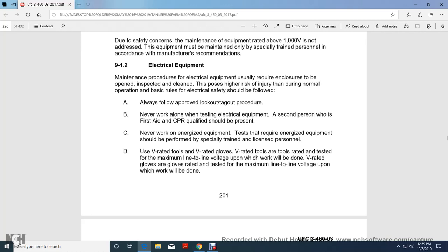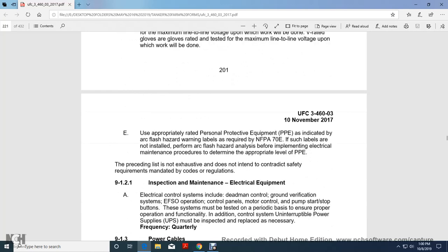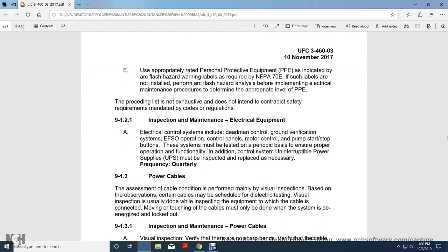Use voltage-rated tools and voltage-rated gloves, rated for at least the maximum line voltage upon which work will be done. Use appropriately rated personal protective equipment as indicated by the arc flash hazard warning label that is required by the National Fire Protection Association 70E. If such a label is not installed, perform an arc flash hazard analysis before implementing electrical maintenance procedures to determine the appropriate level of personal protective equipment. The preceding list is non-exhaustive and does not include or contradict safety requirements mandated by the Code of Federal Regulations.